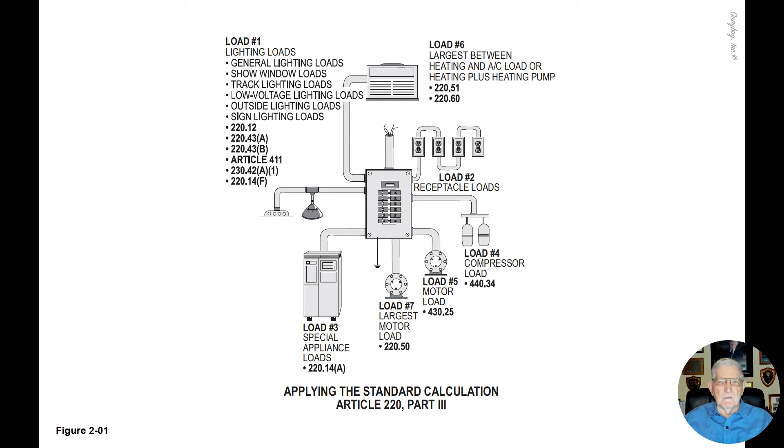The second load would deal with the receptacle loads. The receptacle loads are taken at 180 VA per outlet to load a 20 or 15 amp circuit up. These receptacle outlets can be placed wherever is convenient for the equipment to be cord and plug connected to such outlets.